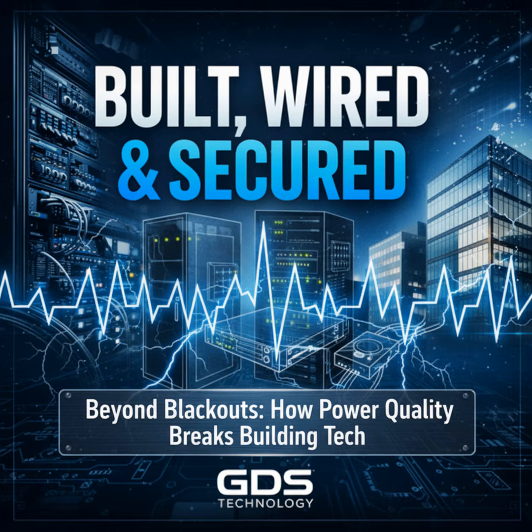4. Prioritize fixes by frequency and impact. Short-term operational changes first, targeted electrical repair second, full capital projects last. 5. Update tenant and procurement standards to require minimum power quality and dedicated circuit information for sensitive loads so problems are addressed at handover. Solid, actionable guidance.